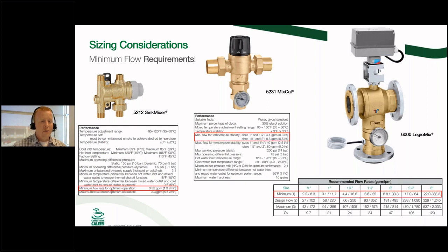phone calls. And I will tell you that every mixing valve under the sun, whether it be a tiny little mixing valve or this great big mixing valve, they're all going to have minimum flow requirements. And the general rule that you can think about is the larger the mixing valve, the larger the minimum flow requirements are going to be. So we've got our little under sink mixing valve here for our single sink applications. We call it our sink mixer. It has a minimum flow rate of 0.35 gallons per minute. This is perfect. It works great for your single lavs. It'll work great for your single temperature touch sensor faucets and things like that.